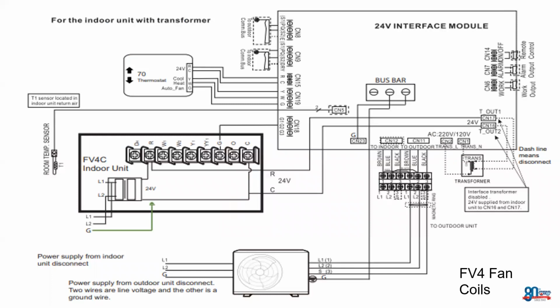So what we have here, of course, you can see in the top right is our 24-volt interface, which we need to purchase separately with this. To the left, we can see our FV4C printed circuit board, and in the bottom center, our outdoor unit. And then right above where our FV4C indoor unit is, our 5-wire third-party thermostat. So let's start at the outdoor unit.